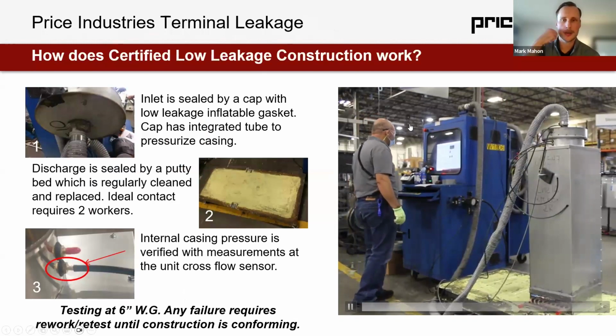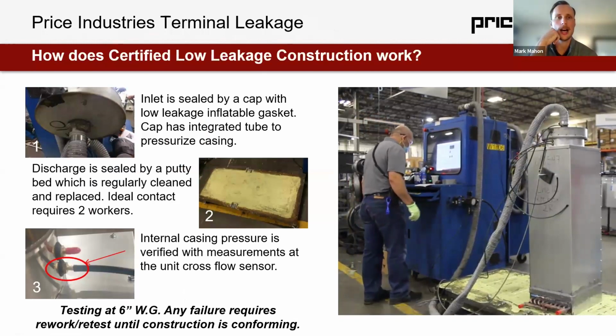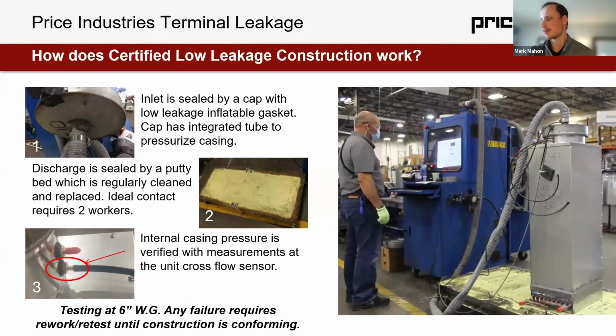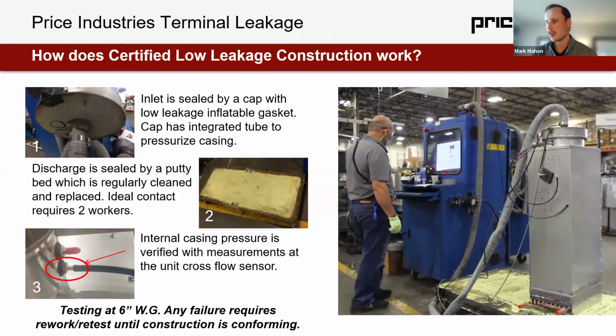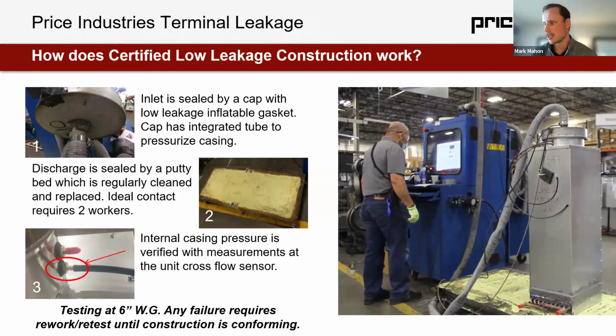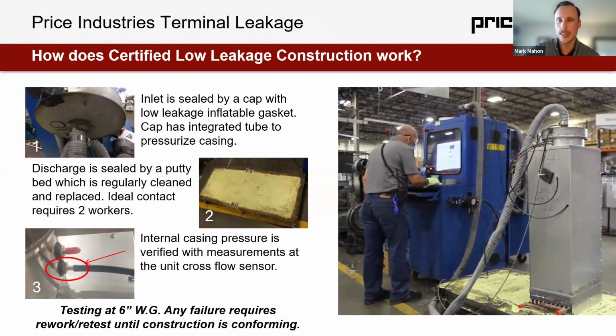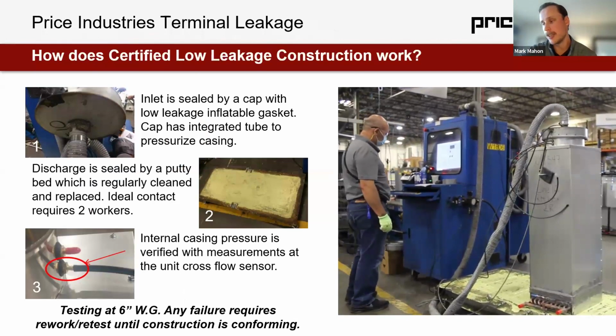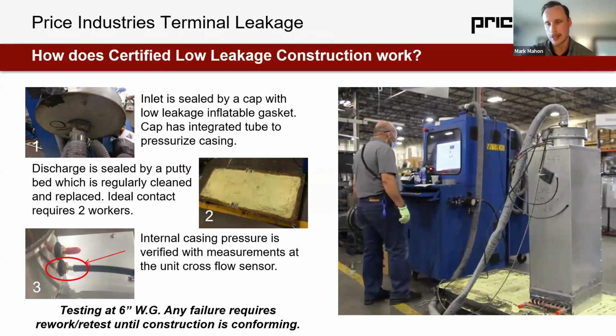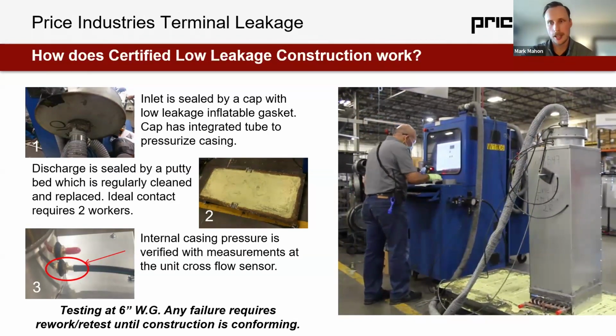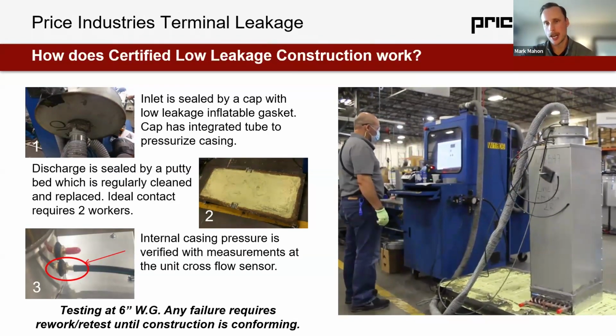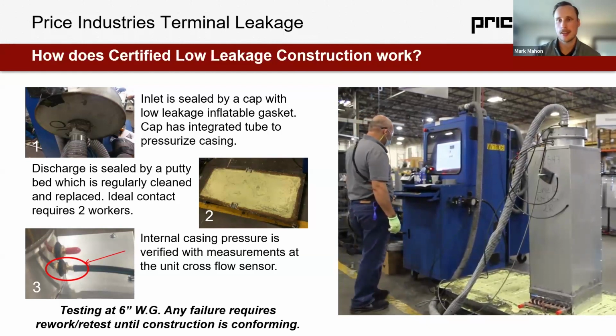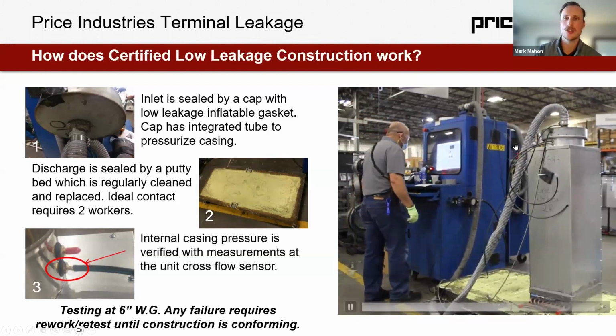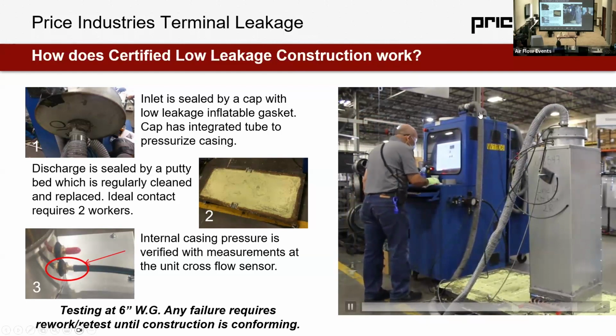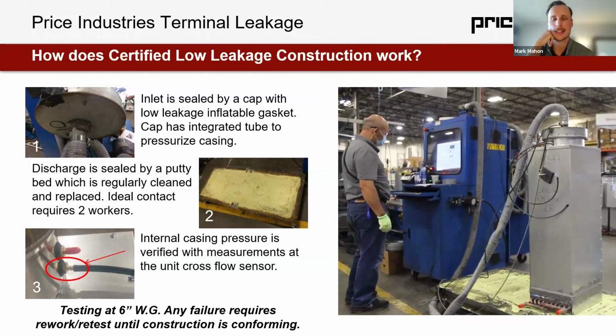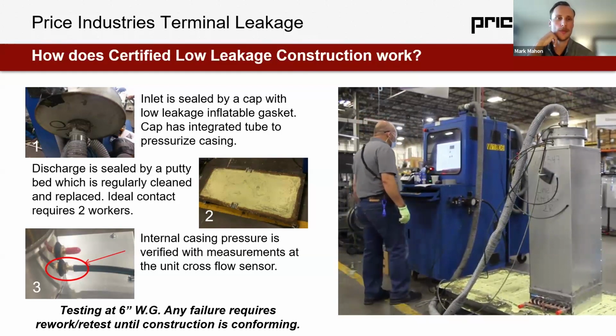Okay, so I want to talk about certified low leakage as well, and a little bit about why you might choose to specify it and how it works. The first thing I want to note with this leakage test that we're seeing on the right-hand side of the screen is that the factory leakage test and the field leakage test are essentially the exact same thing. We're sealing the equipment, pressurizing it up to 6 inches, and measuring through this tube the additional CFM required to hold that pressure. That's how we figure out the leakage of the equipment.